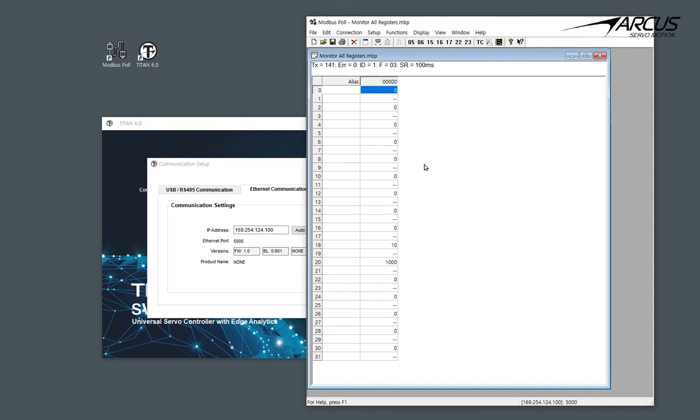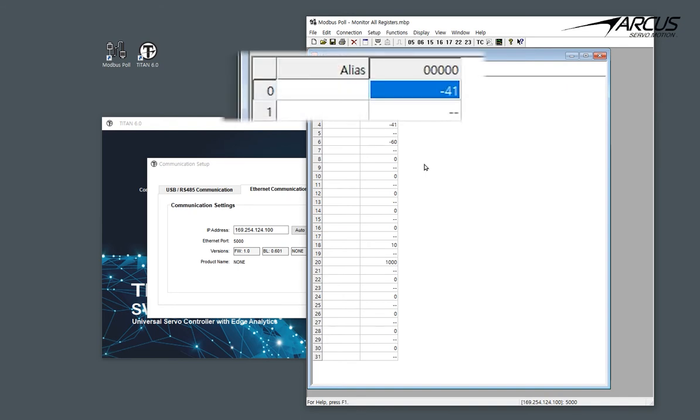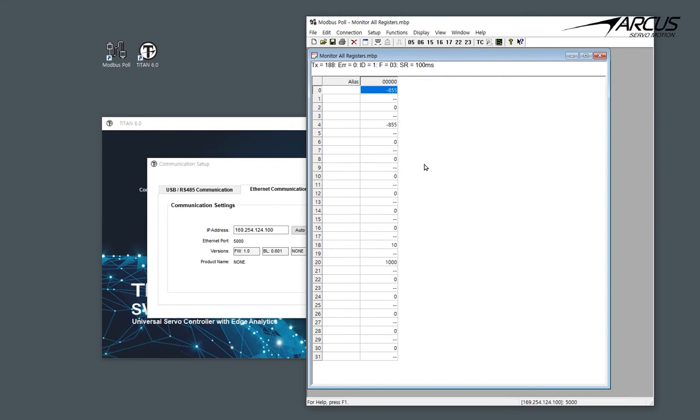Let's manually rotate the motor and see that the position counter changes at address 0, which is the encoder counter. Now let's set the motor speed, acceleration, jerk, and the profile type using the Modbus function 16.